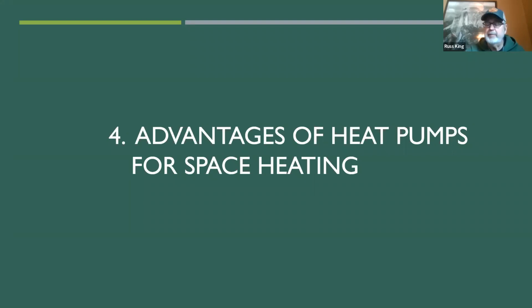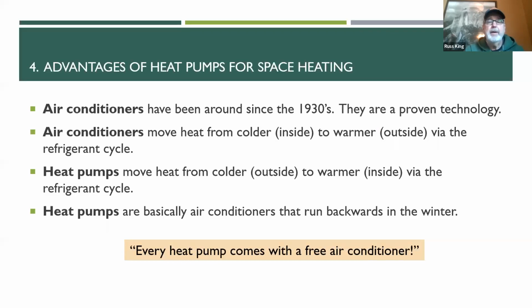So the advantages of heat pumps for space heating. As I said, air conditioners have been around for a long time, since the 30s. They're a proven technology. Air conditioners move heat from the colder inside of the house to the hotter outside. So they're extracting BTUs from the house that are coming in from the outside. Heat pumps are just air conditioners that run backwards. They extract heat from the cold air, they compress it, and they put it into the house and heat the house by moving BTUs from the cold air to the inside, okay? All right, so heat pumps are basically air conditioners that run backwards in the wintertime.